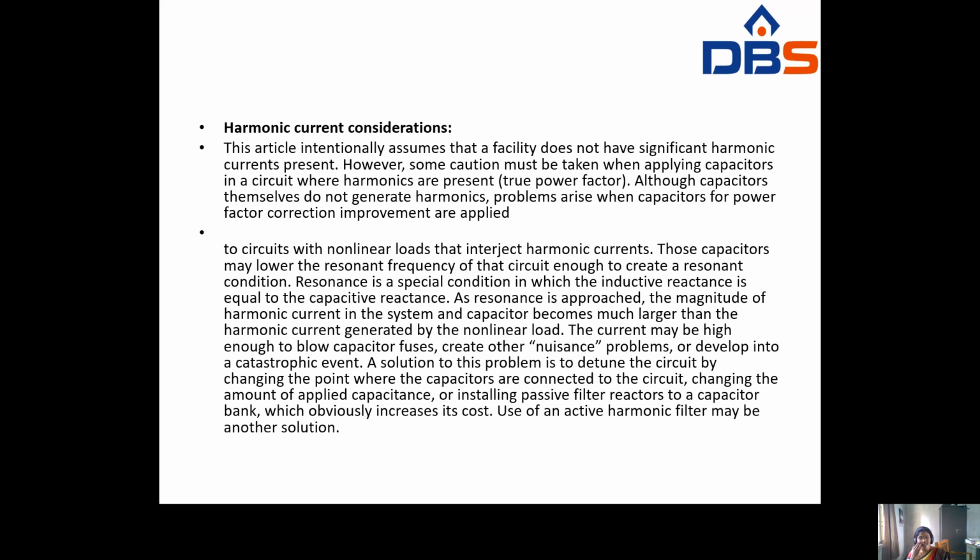See here, this article intentionally assumes that a facility does not have significant harmonic currents present. So there will not be a large amount of harmonics, only a small amount. However, some caution must be taken when applying capacitors in a circuit where harmonics are present. Why are you introducing the capacitors? To improve the power factor value.